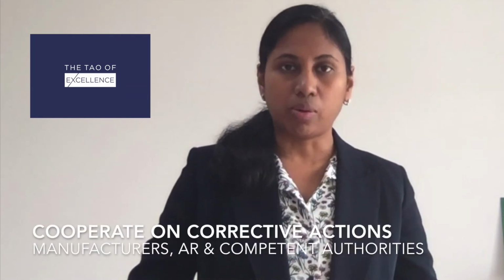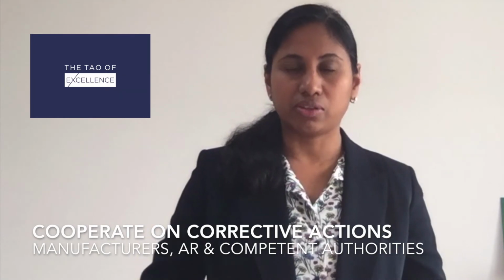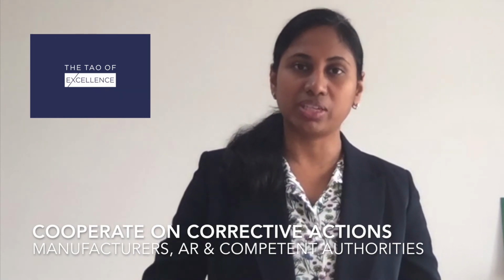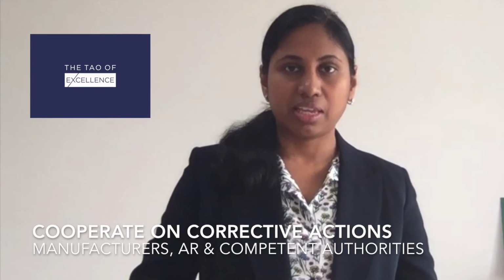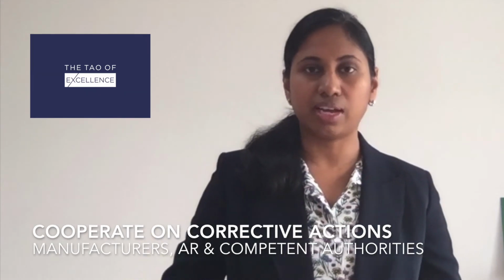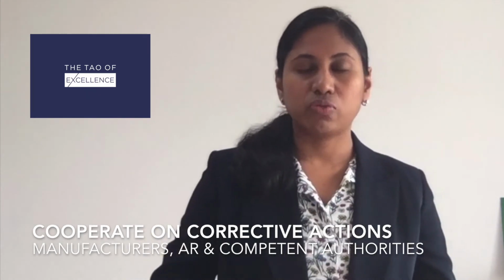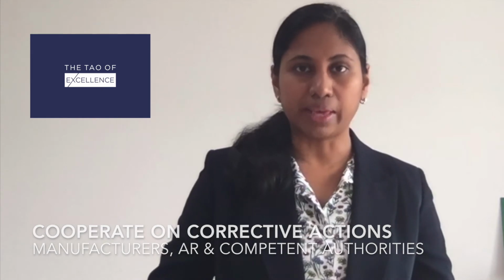If the importer considers that they have placed a device on the market which does not comply with the regulation, they shall immediately inform the manufacturer and their authorized representative. They shall cooperate with the manufacturer, the authorized representative, and the competent authorities in taking any corrective action to bring the device into conformity or to withdraw or to recall it.